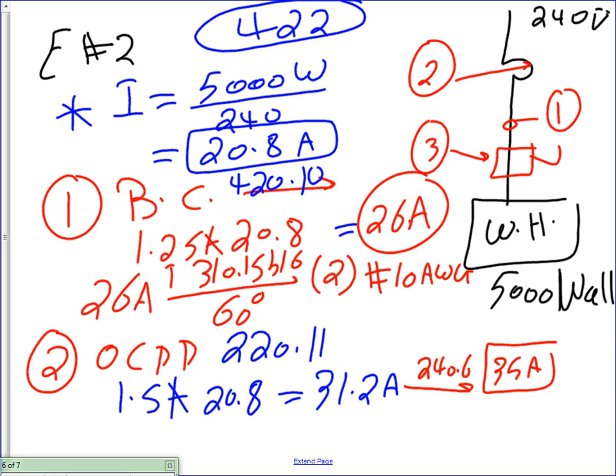What happens if I put a 35 amp on a number 10? Is it allowed by code? It's not a motor. Is it allowed by code? No. So you have two options to choose from. Either you make this 35, but what do you need to do to your conductor? Go to number 8, or instead of going to 31, can I go down? Yes, there's nothing wrong with going down, right? So I go down to 30. So two options. The code allows me to go up, but I can also go down to 30 amps.